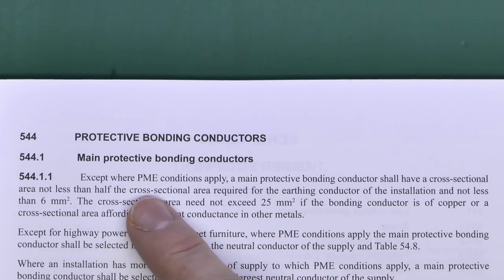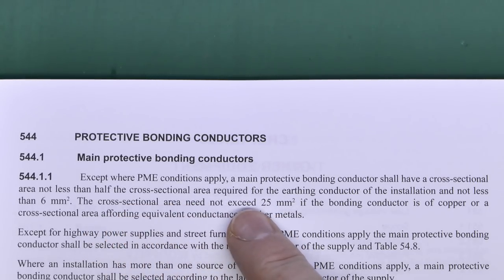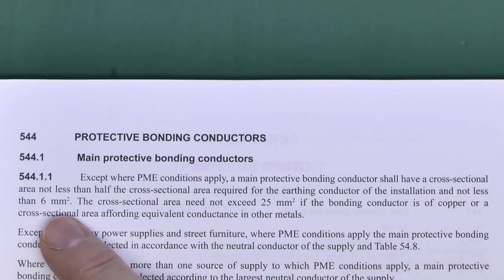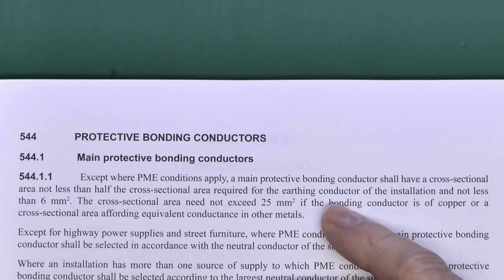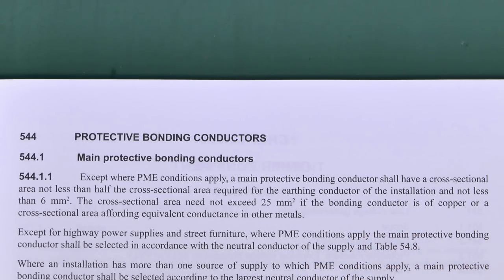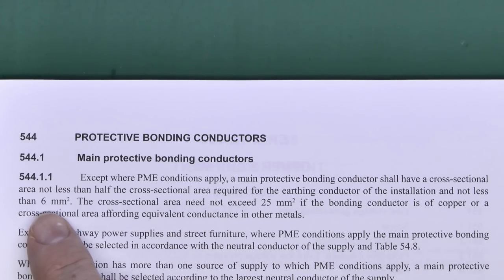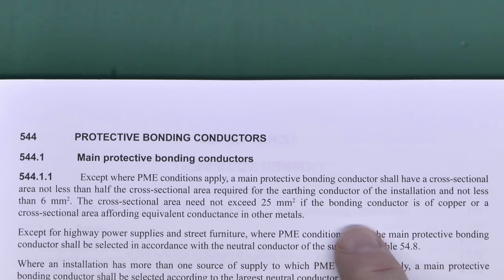Regulation 54411 states that except where PME conditions apply, the main protective bonding conductor should have a cross-sectional area of not less than half the cross-sectional area required for the earthing conductor of the installation, and not less than 6mm² in any case. So if you've got a 16mm² earthing conductor, half of that is 8mm², which is more than 6mm², so 8mm² would be fine. But in reality you can't buy 8mm², so it usually ends up as 10mm². It need not exceed 25mm² if made of copper.